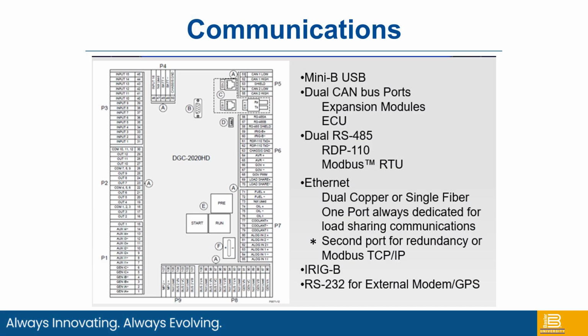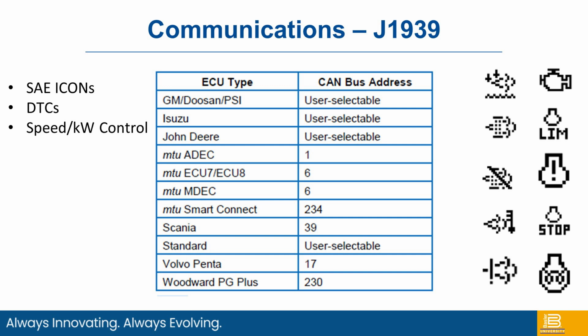Talk a little bit more about the communication side of things. We covered a few of these things already, but as you can see, here are your communications ports on the back. J1939 communications for your electronic engine control. We follow all the SAE standards, so we are not only communicating with the ECU, but we actually have the capability of displaying the Tier 4 and Tier 4 final and Stage 5 icons that are standard for SAE. We also can read the DTCs, the diagnostic trouble codes, from the ECU. A lot of the times operators at the genset side of things don't have the software tools to be able to look at what the DTCs are in the ECU. The DGC-HD will actually pull those DTCs and display them on the HMI. And then with that J1939 CAN bus, we also have the capability of controlling speed and kilowatts to the engine.